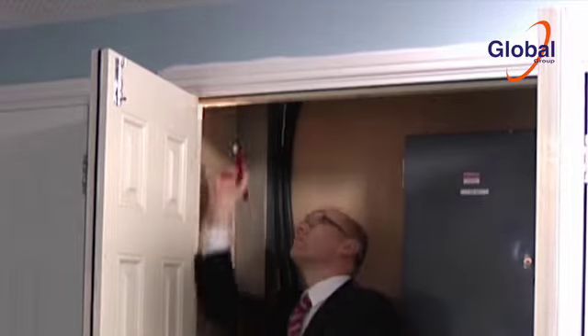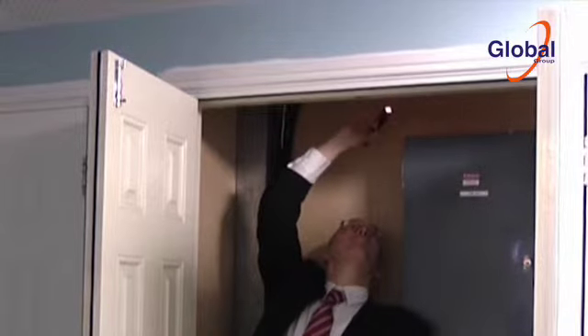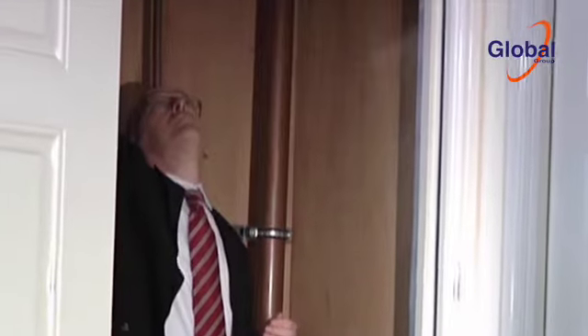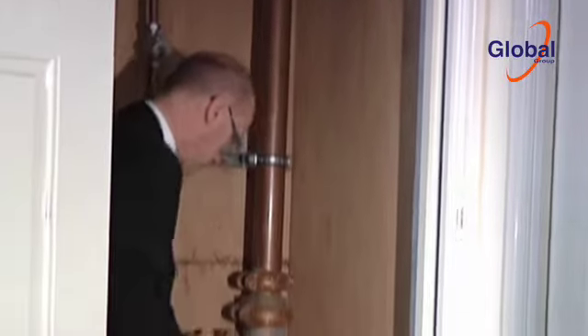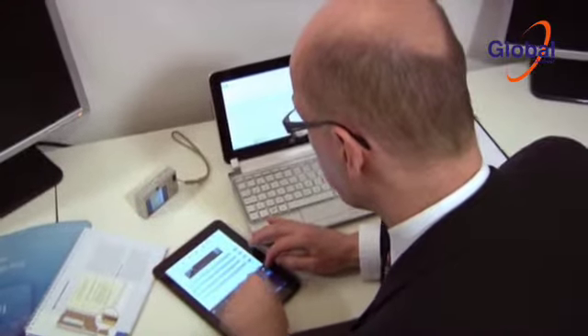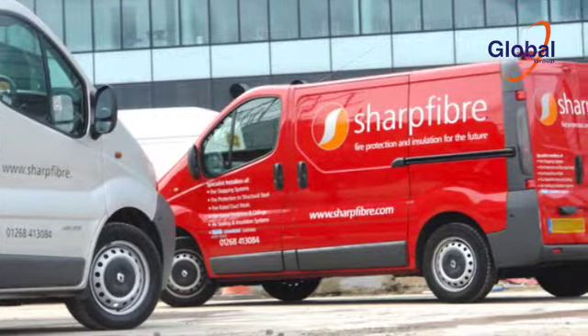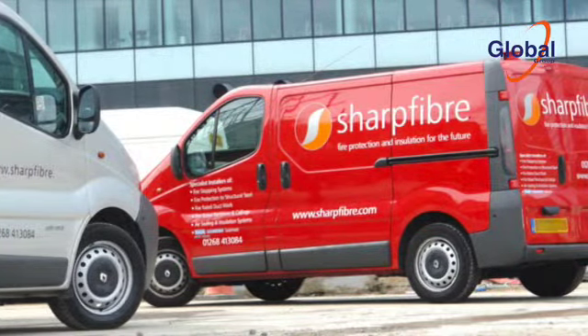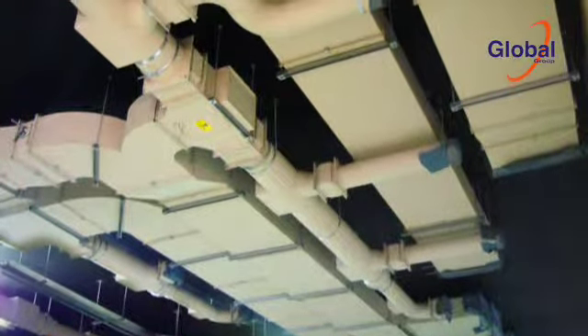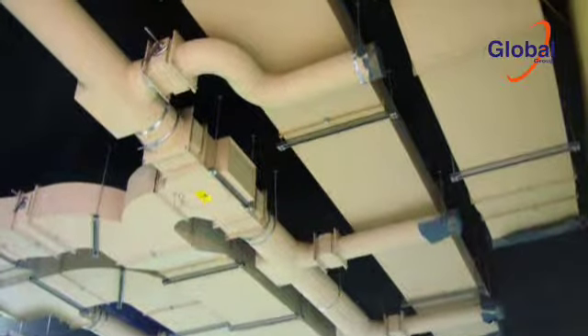Sample inspections of the protected shaft should be undertaken at access points and where they pass through compartment walls and escape routes. If an assessor is not confident that an enclosure provides adequate separation, it should again be recorded in the risk assessment, and a more thorough, invasive third-party inspection should be considered. All fire-resisting ductwork, dampers and enclosures must be checked on a regular basis, and records of all checks must be maintained.